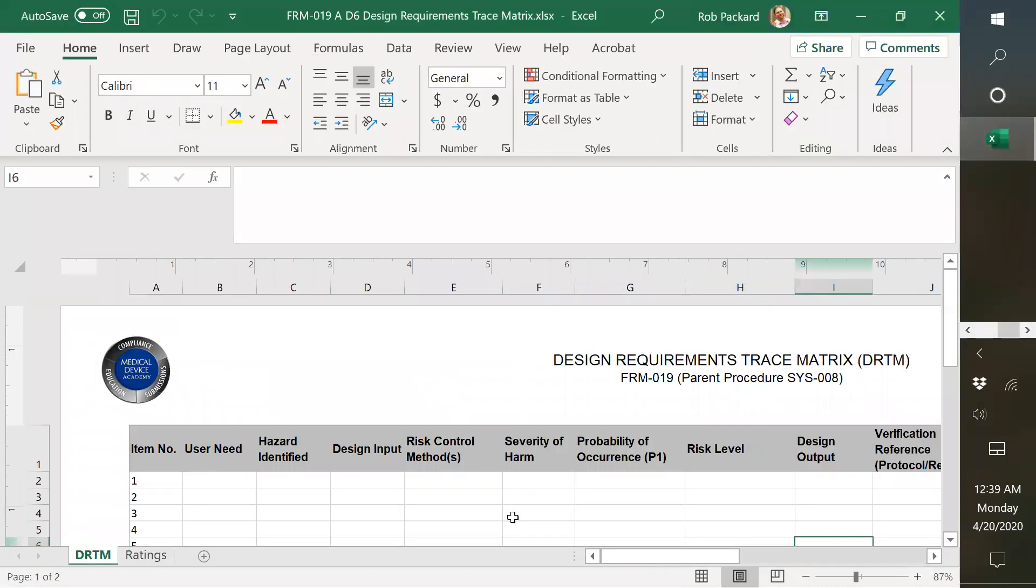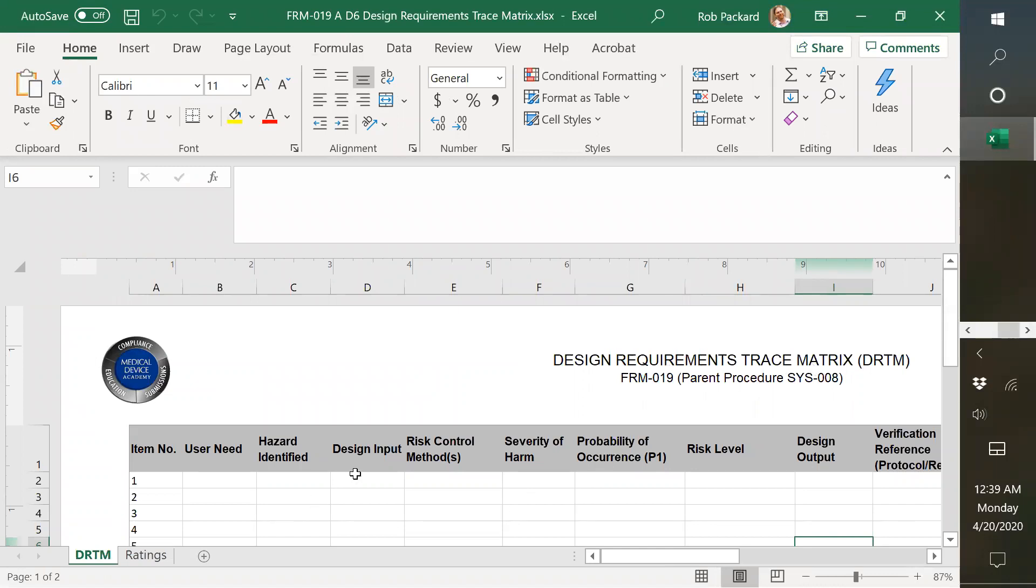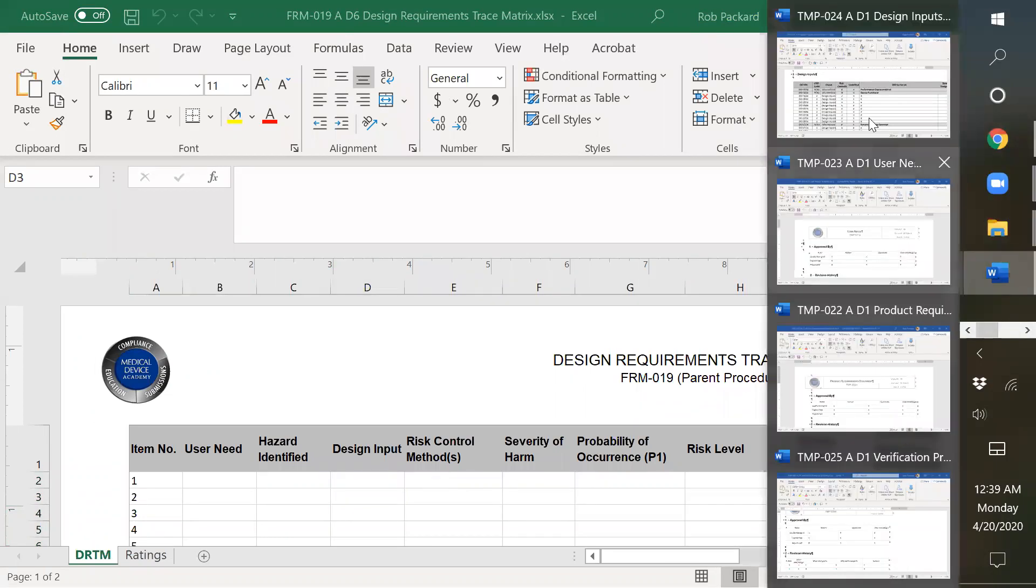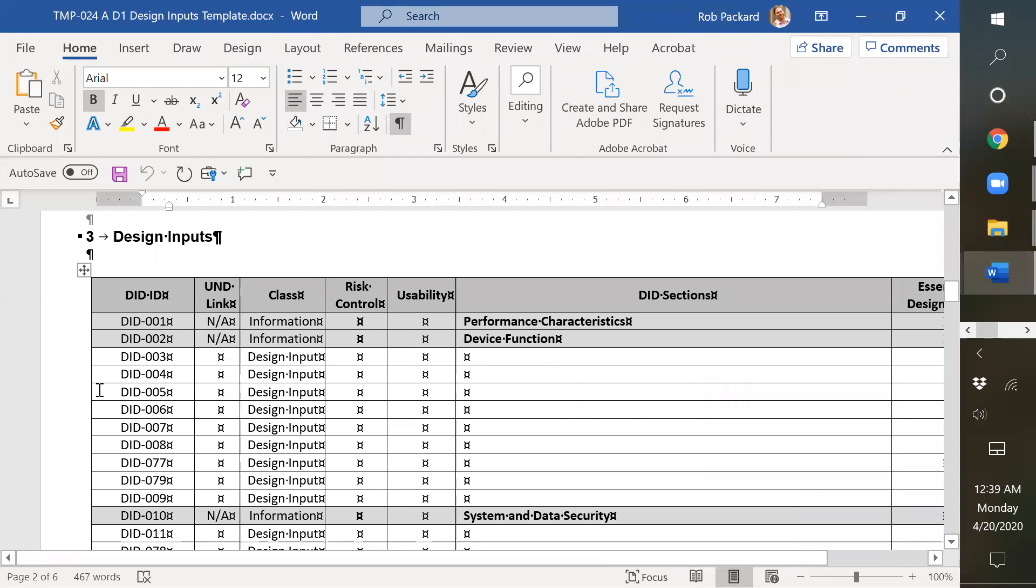So we've got a combined design requirements traceability matrix, and you could put design inputs here. You could also put hazards, or if you need more room, you could just reference the document where it can be found and what line item it is. And then you'd put it in that other document here and indicate what ID it is.